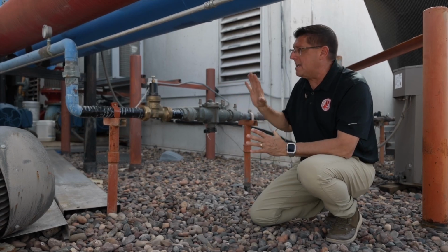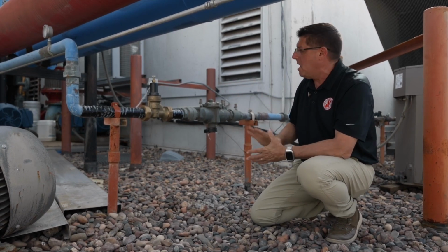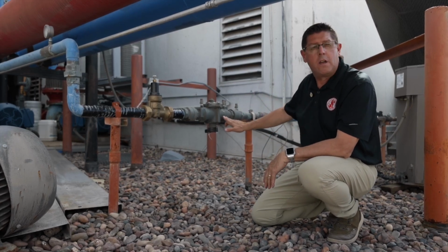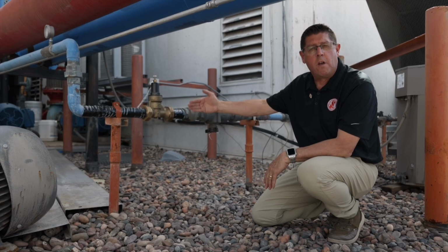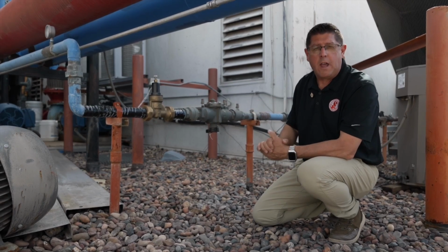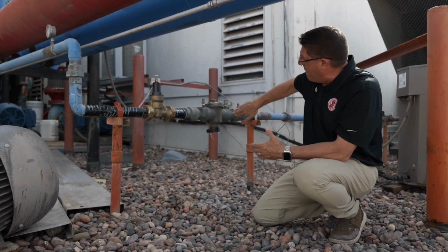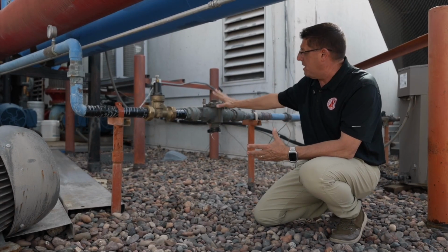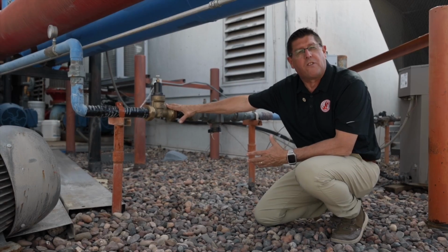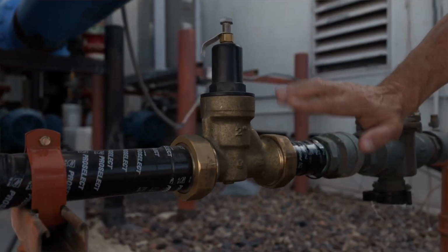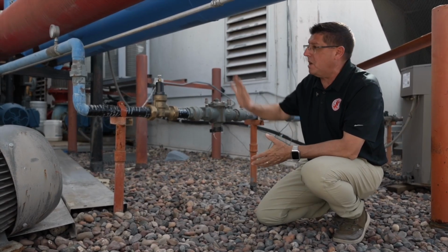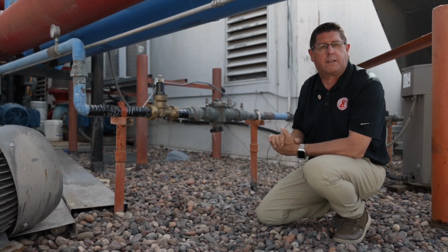So when you're looking and identifying these backflow prevention devices, the first thing I look at is look for leakage, and I want to make sure my arrow is pointing in the flow of the water for which I need it to travel. And then it prevents any water from going back this way past this device. In addition to this backflow preventer, I also have a pressure reducing valve that drops our pressure down to the using pressure that we need for this appliance. But this is the key element that I'm looking for in my backflow prevention of this cooling tower and protecting this building.